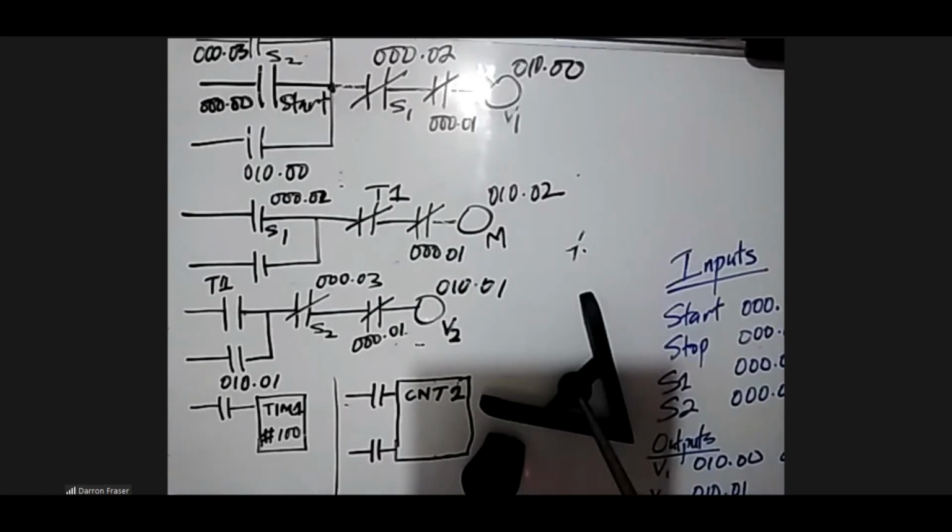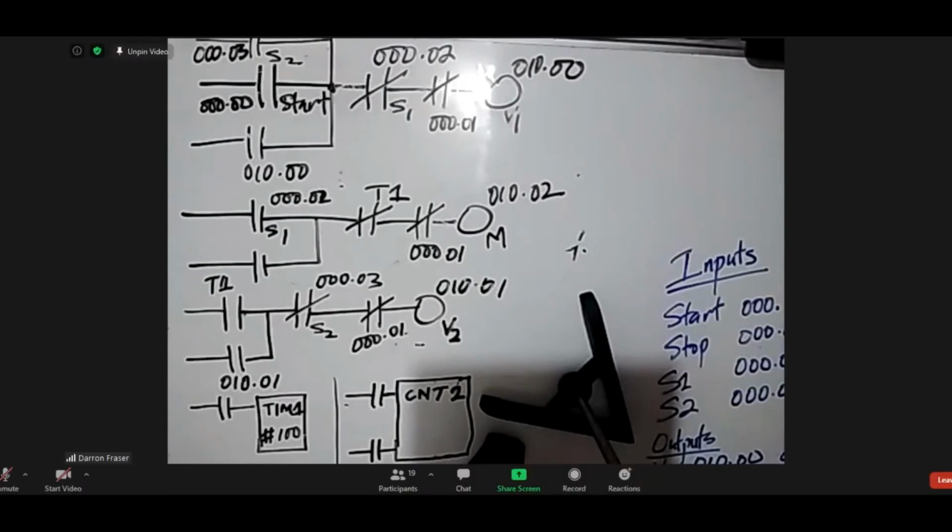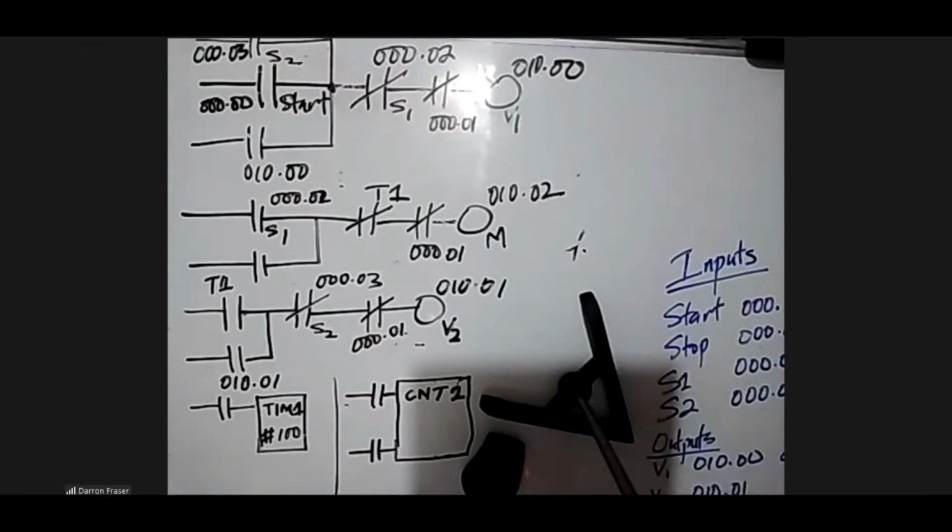Everything is fine, everything is okay. You sure there's a problem? No, nothing is wrong. That's how it behaves. And then you say, but it's not working, nothing is going on. So what is the problem? Nothing, there's no problem. So whenever you do that, that is something you need to bear in mind. You cannot give the timer and the counter the same address. If it's timer 1, counter 2. And if you have a next timer, you have to put 3, and so forth and so on. So that's the first thing.